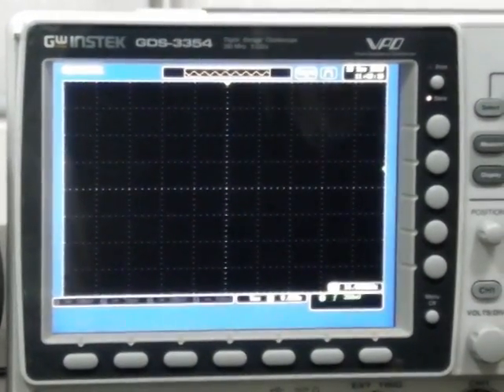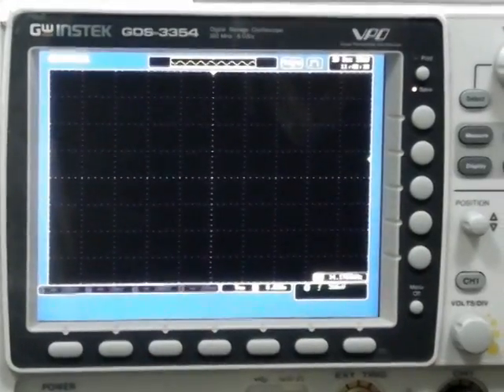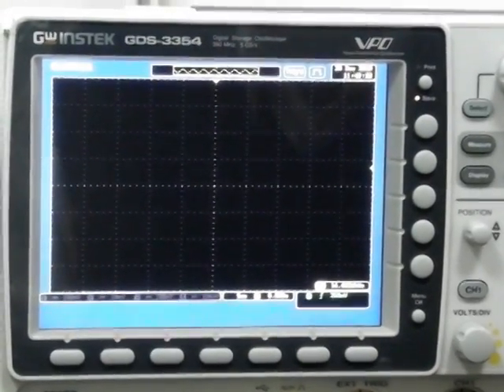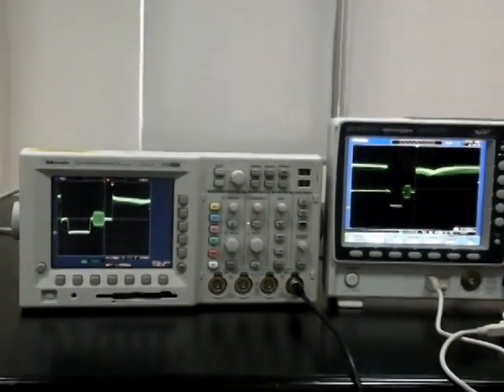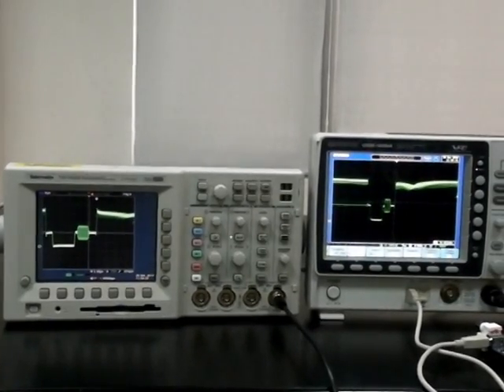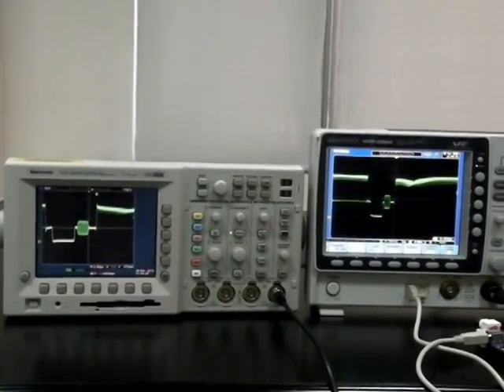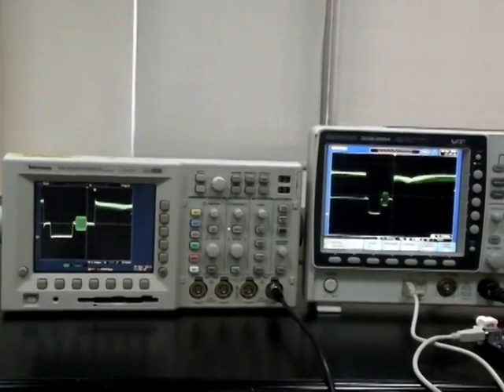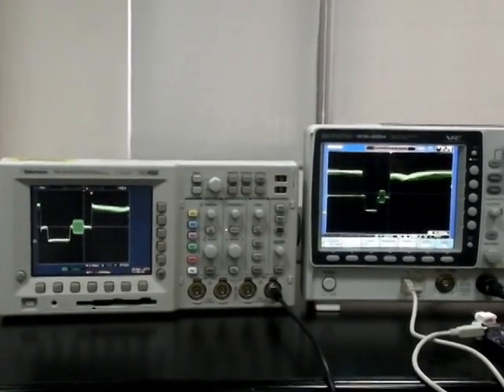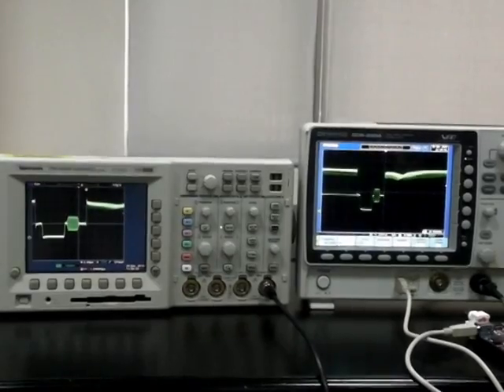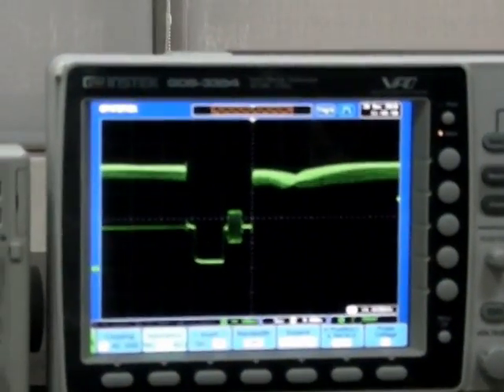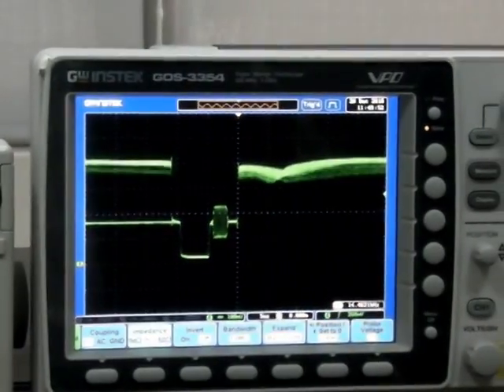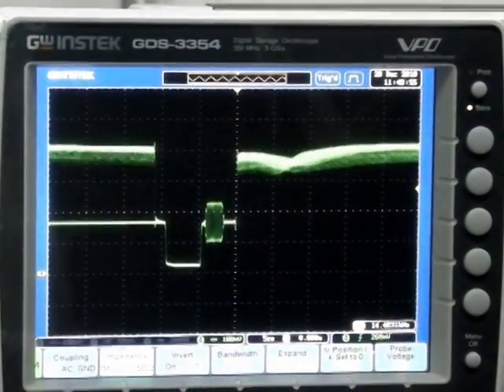First, we will demonstrate the waveform capture technology used on the GDS-3000. Connect a video signal to channel 4 on each of the two instruments and turn channel 4 on for both instruments. With VPO waveform capture technology and a 5G sampling rate, the performance of the GDS-3000 is comparable to the TDS-3000. In addition, the larger 8-inch SVGA screen allows you to easily view any changes in a waveform.